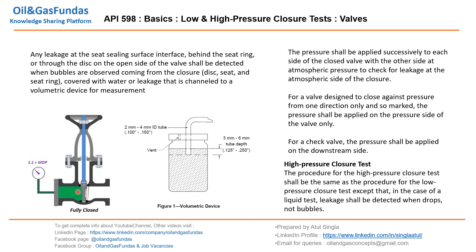For the check valve, pressure shall be applied on the downstream side — whichever side we want to prevent backflow from, we apply pressure on that side. For the high pressure closure test, the procedure is the same as for the low pressure closure test, except that in the case of a liquid test, leakage shall be detected when drops are observed, not bubbles. This is the basic difference between low and high pressure closure tests.